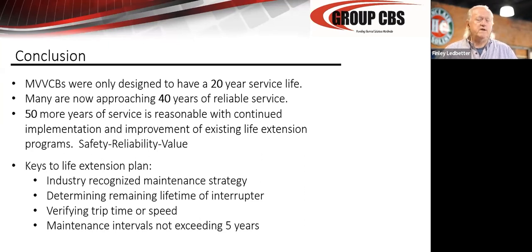The other reason we have to keep it in service, or actually two reasons, is the gear was installed and now equipment has been built around it, and it's hard to get out now. Number two is the equipment was installed and the cables were run to it. And if you go in and bend these cables, disconnect them, flake them back, pull the old switchgear off, install new switchgear, chances are you've damaged the cable. These cables have been sitting still for 30, 40, 50 years, and physically moving, flexing, disturbing these cables is a very bad idea.